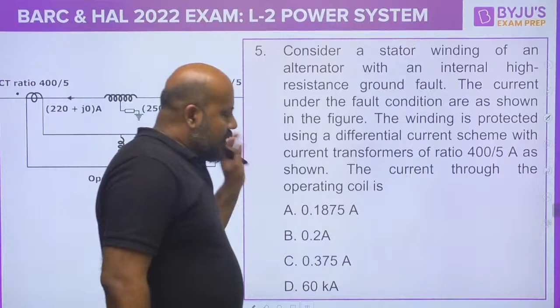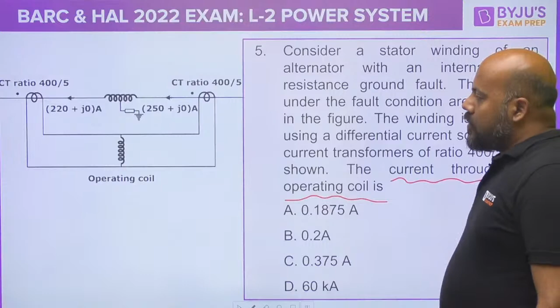When the current is present in the relay operating coil, and if this current I1 is more than the pickup current, what is pickup current? Pickup current is the minimum current above which the relay operates and sends a trip signal to the circuit breaker. So if this I1 current is more than the pickup current, this relay is going to operate, and the relay operating means the contacts of the circuit breaker will open, and the apparatus or the equipment is going to be protected against this fault. This is how this differential protection scheme works.